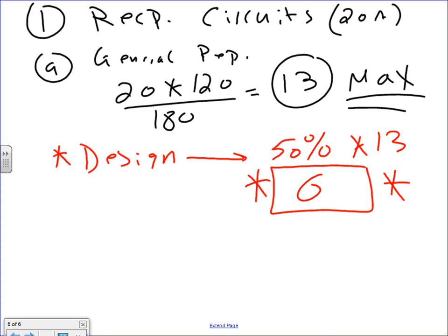Are they stipulating that for all of them or just certain ones? No, there are certain areas. They have a note number two next to them, mainly what they call technology receptacles. A technology receptacle, guys, is the one where you sit in your cubicle and plug in a laptop like this. Now, how much power does a laptop like this draw? I guarantee you less than 180 volt-amps for this receptacle. But there are so many of them, and you can plug in so many things, so we're assuming we're going to see the max.